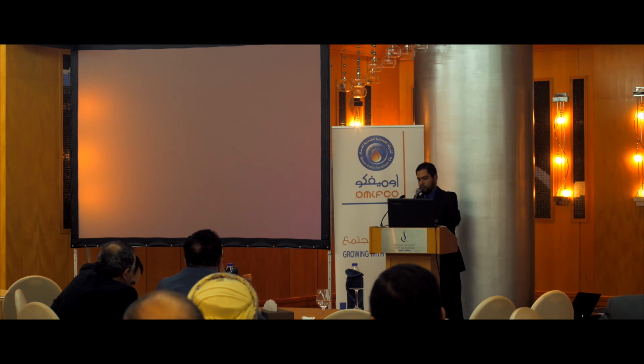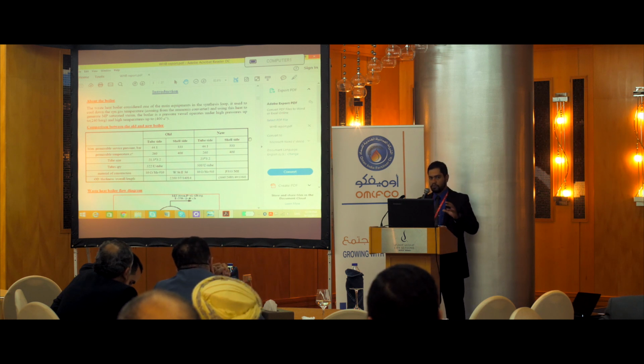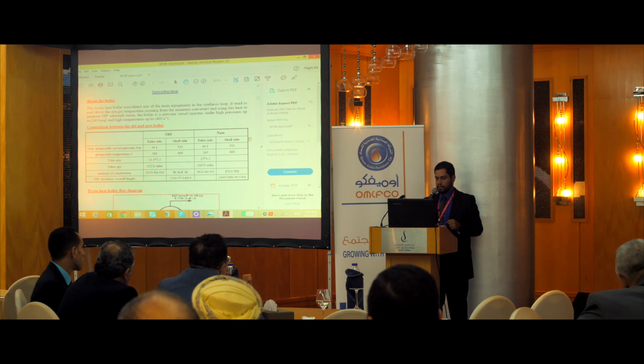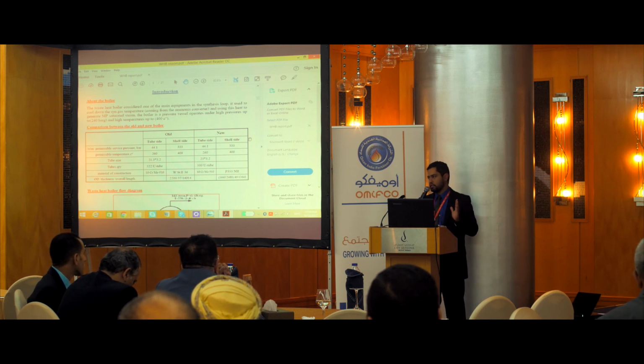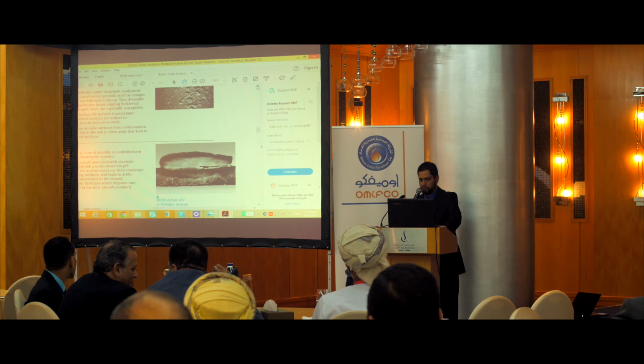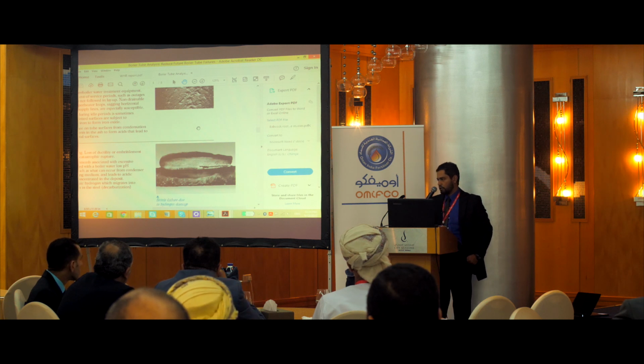We have another proof of the pH decrease in the auxiliary boiler of the factory. We experienced a failure because of hydrogen attack in the generating tubes of the auxiliary boiler. The shape of the failure was window-door type, the typical shape of failure in the hydrogen attack case. This is the failure shape of the hydrogen attack because of the loss in the value of pH. The typical value is 9.5, and it decreased to 4.5.